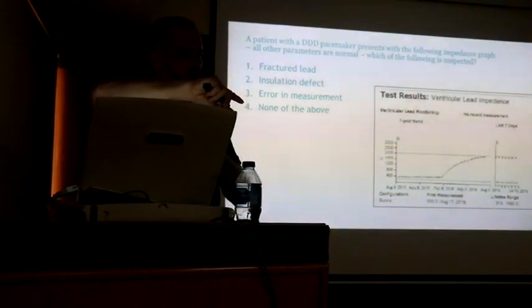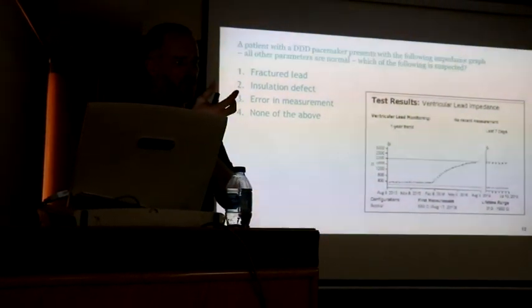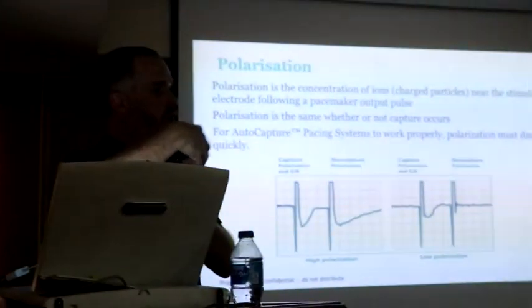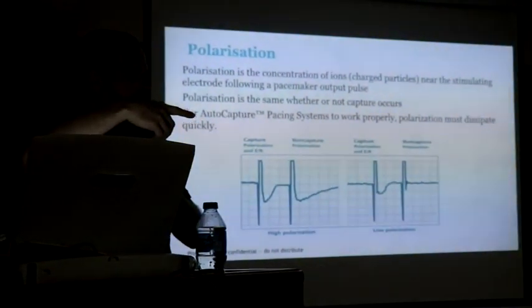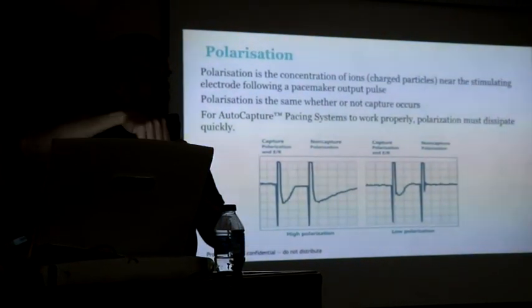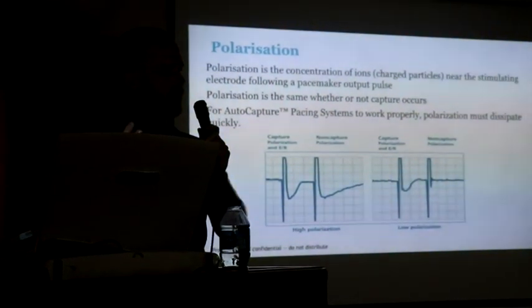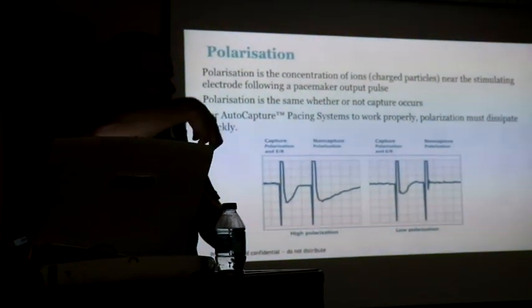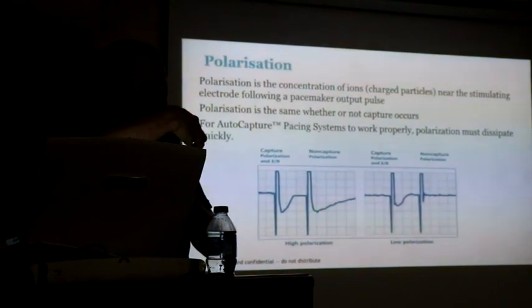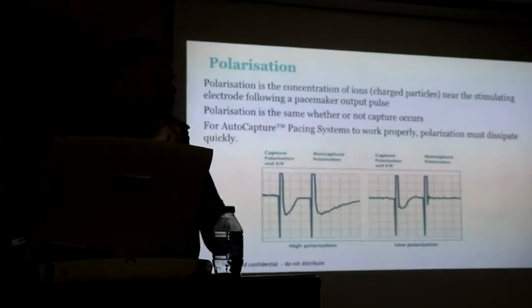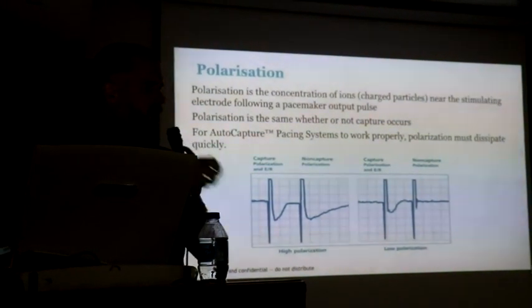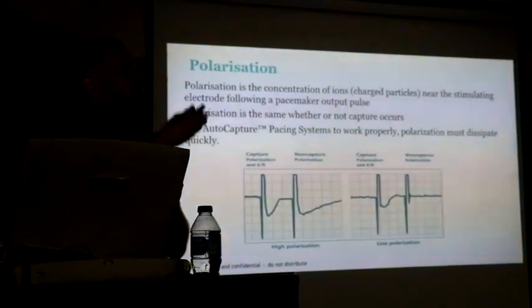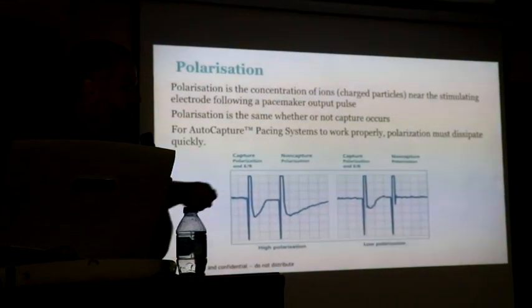But I suppose lots of you do echo, and you do an echo on somebody and you see calcium deposits in the valves and wherever else. So it's like that. So you're not using that whole surface area. The thing that reduces polarization noise is the huge surface area. But if there's air still sticking on the surface of the electrode, you're not using your whole surface area. So you create more noise. When that air dissolves off, then it turns into this.